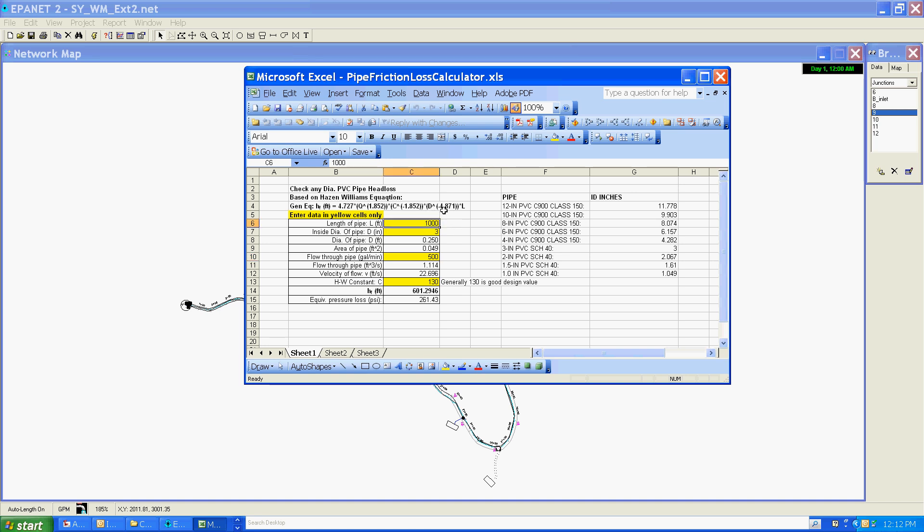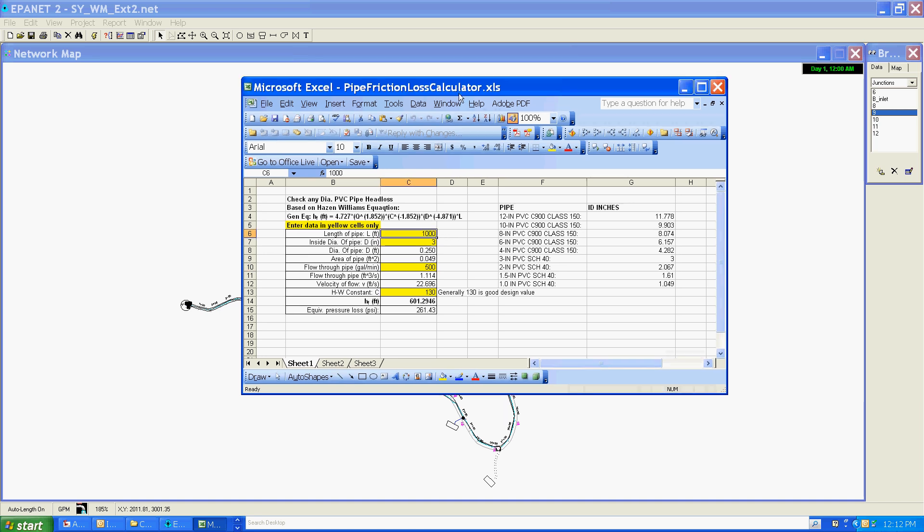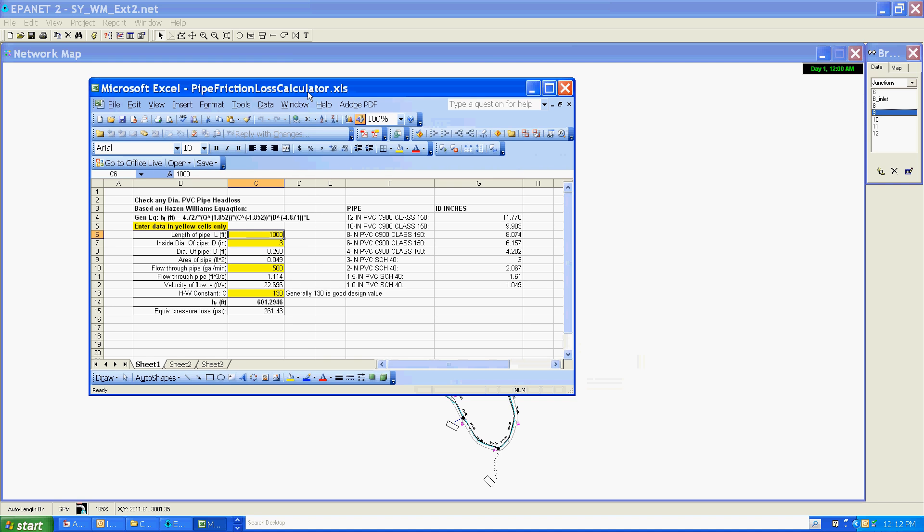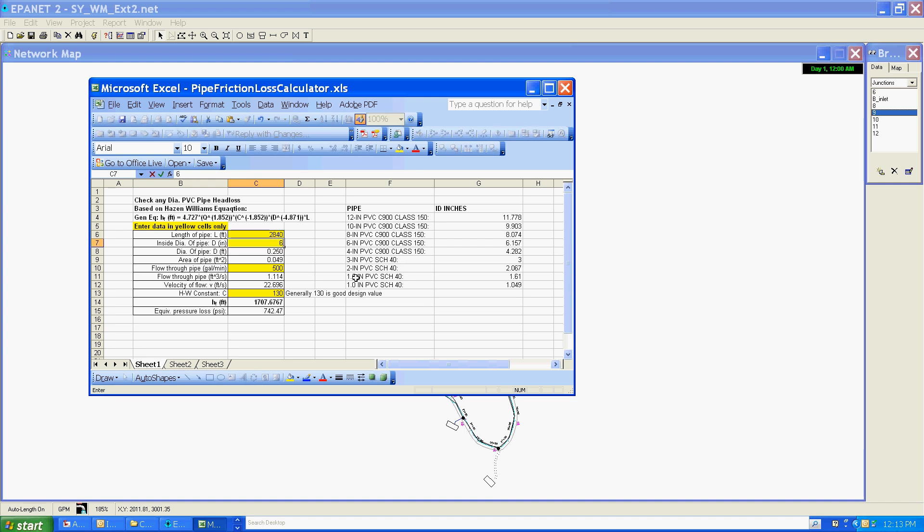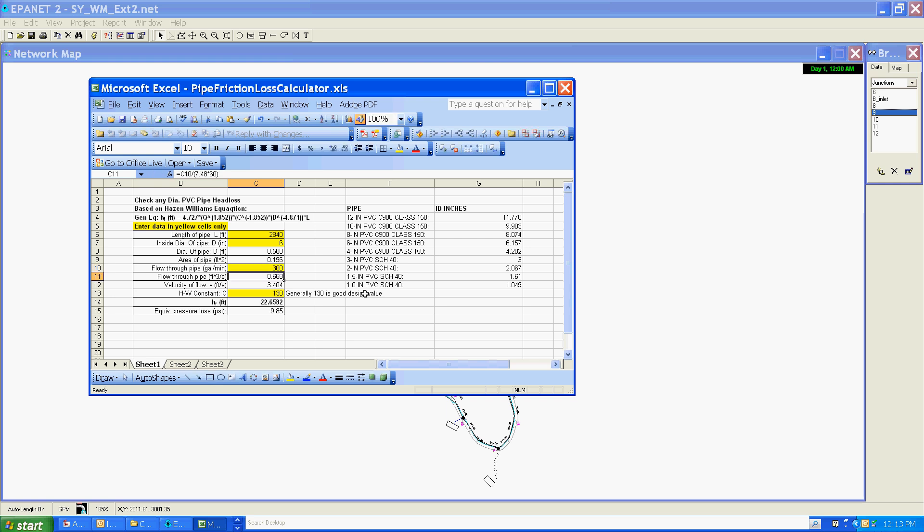The length of pipe between the tank and that node I went through, and on the properties added up the pipe lengths, is about 2,840. I'm going to set the pipe diameter to 6, which is just a rough estimate. As you know, the inside diameter of the pipes aren't exactly the nominal size, but for this model we're just using 6. I do have others over here for actual types of pipe. The flow I set in there was 300, and I've left the roughness coefficient to 130, as I did in the model.